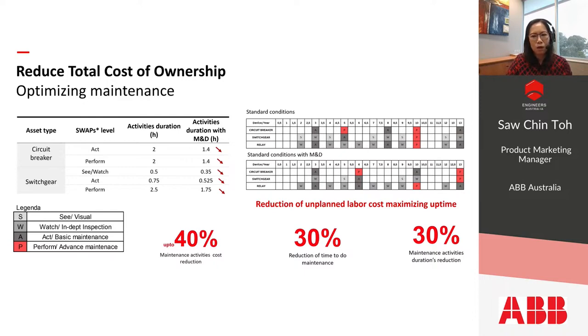Watch is for a more in-depth inspection into a certain component or parts of the switchgear, which may involve de-energizing the panels. Act is to perform the basic maintenance, for example, cleaning, lubrication, or function tests of the equipment. And perform is the advanced maintenance, which includes repair and reconditioning or refresh of that particular equipment.